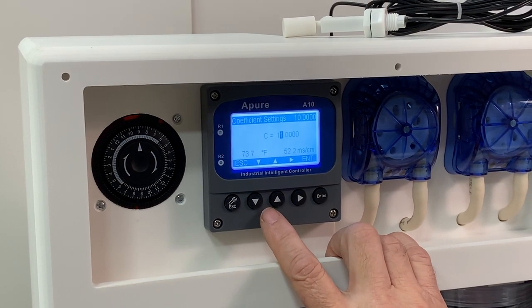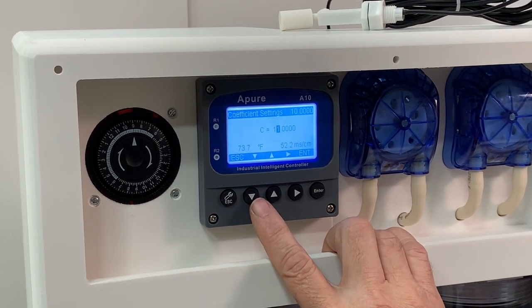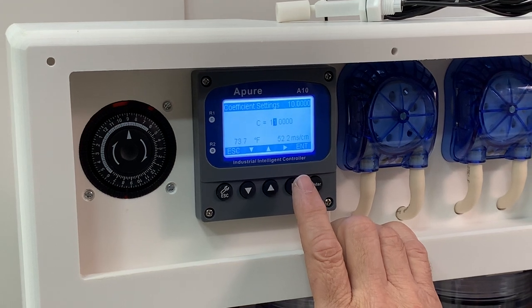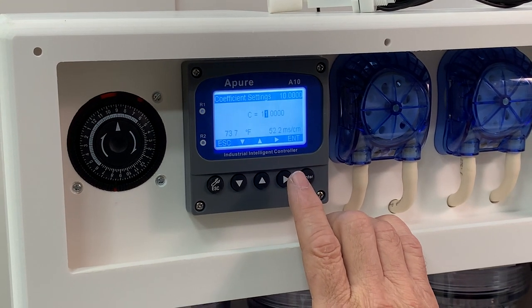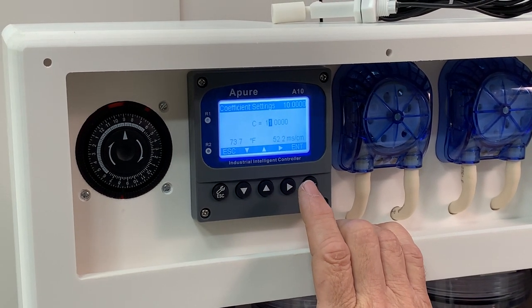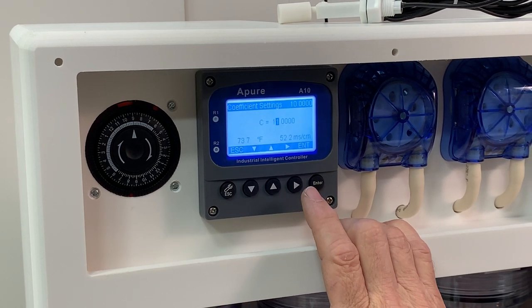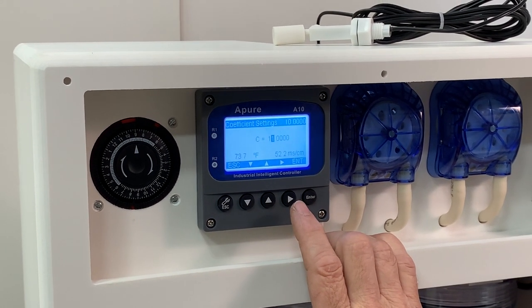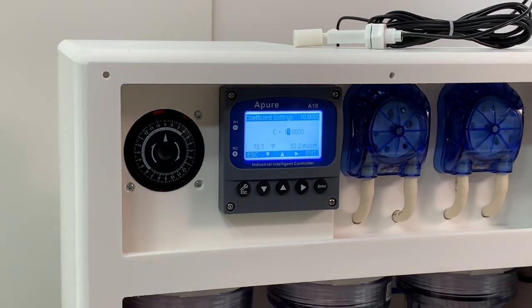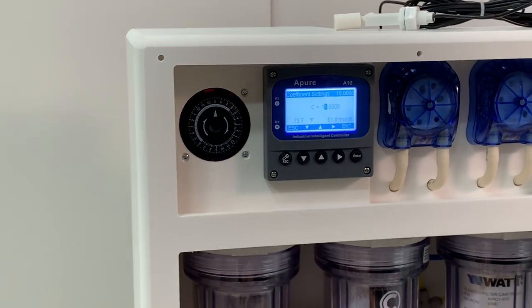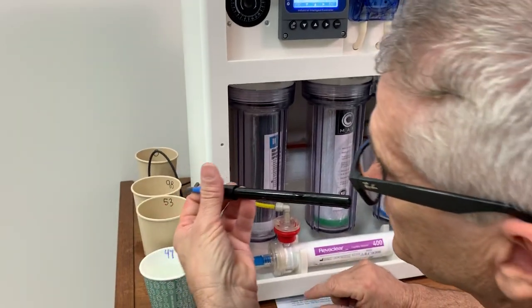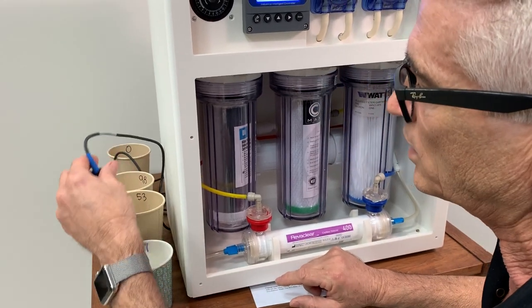I don't recommend that you do that. You really don't need to. If it does need to, it usually indicates that your probe is clogged or needs cleaning, and that's done simply with lemon juice. Very carefully, you take a brush and brush inside this area in here and clean that out. I like to just blow on it with DI water.